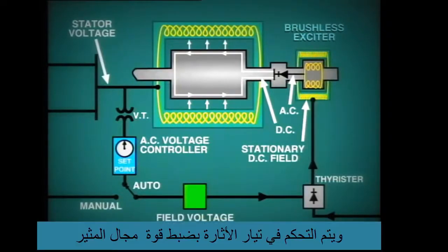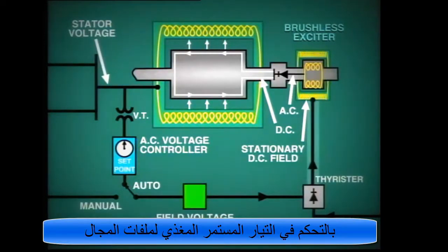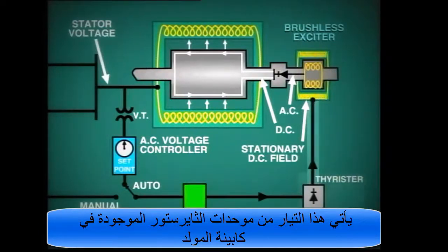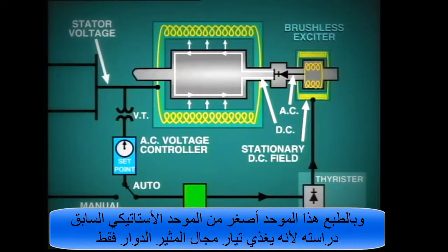Control of the DC excitation current is affected by adjusting the strength of the exciter magnetic field, and this is done by controlling the DC current flow through the field winding. This DC field current is supplied from a rectifier which is located in a nearby cabinet. Of course, this rectifier is much smaller than the static rectifier previously studied, because it is only supplying field current to the rotating exciter.